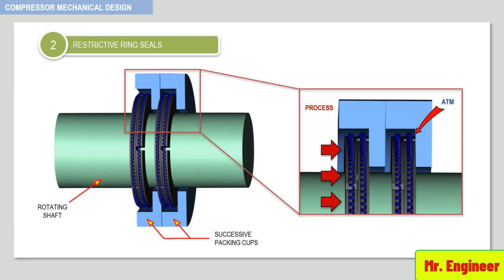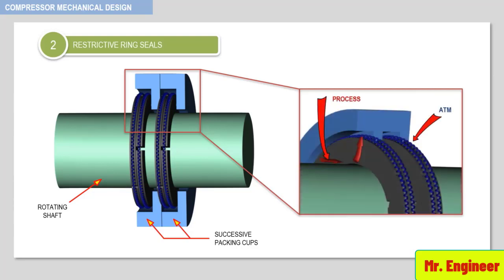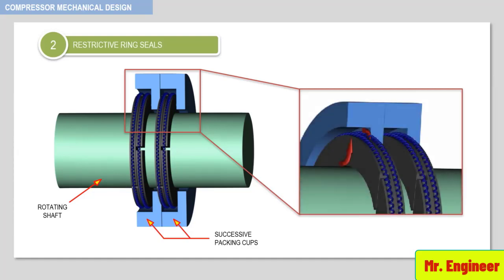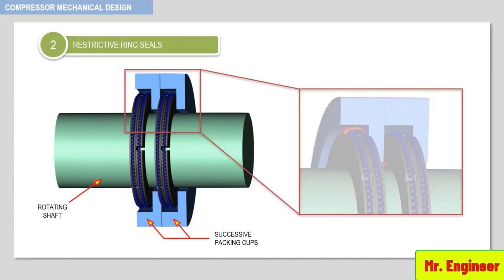This pushes the packing rings against the packing cup to reinforce the sealing action. However, there is a small entry of process gas from the process side to the atmospheric side through the tiny space between the segments in the rings and the clearance existing between the packing ring and the packing cup, as depicted in this simplified animation, with red arrows representing the process gas as it leaks through the seal.